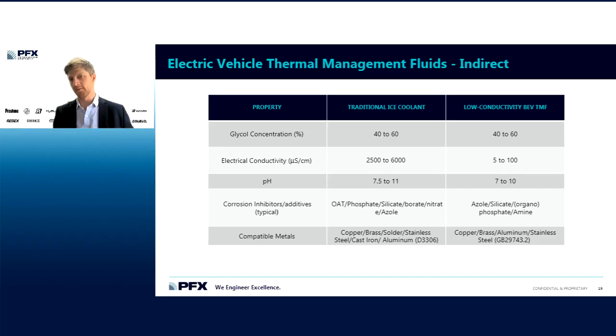Where we start to see a little bit of deviation is electrical conductivity. Traditional coolant is 2,500 to 6,000 microsiemens per centimeter, while low conductivity coolant is going to be in the range of 5 to 100. The pH range is also a little bit tighter for low conductivity BEV fluids, generally due to the lack of ability to put ionic bases into the formulation that would get you to those higher pHs.